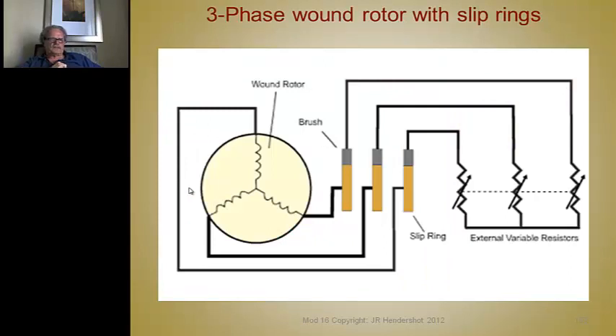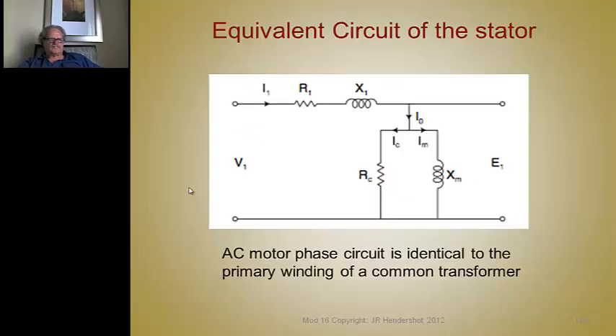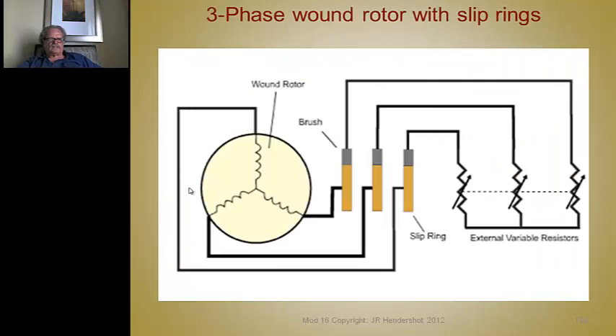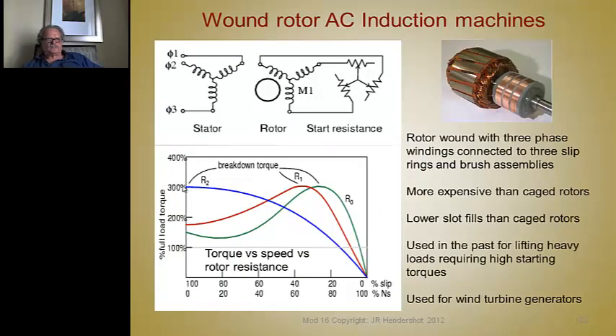So this is what I was talking about before. There's your wound rotor, and your brushes and your external variable resistors are used to adjust the starting torque. So in this case, you use the series resistors to get the starting torque, but then you short those out so that when you're up to speed, it operates on this slope line.